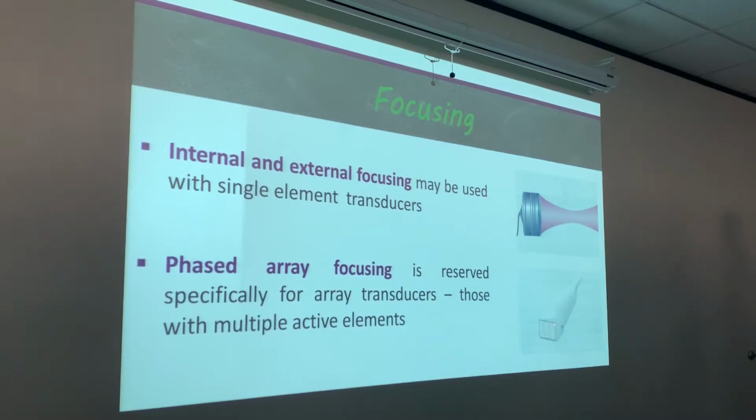You can see right here, remember guys, I told you, this is one PZT strip, but this PZT is broken down into those vertical elements right here. So each one of those is an active element. Each active element has its own electronic signal connected to it. So it's not just one electronic signal, it has its own wire that's going to send an electric signal to it. And that's how we're able to electronically focus and steer that beam.